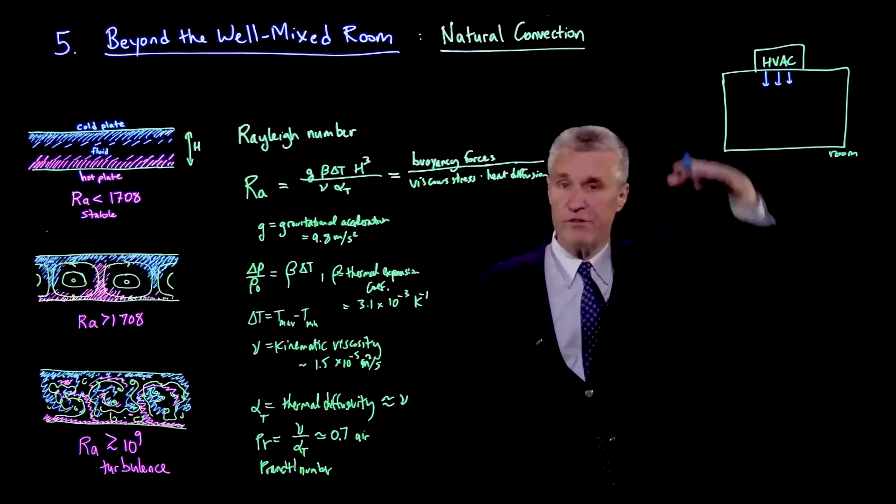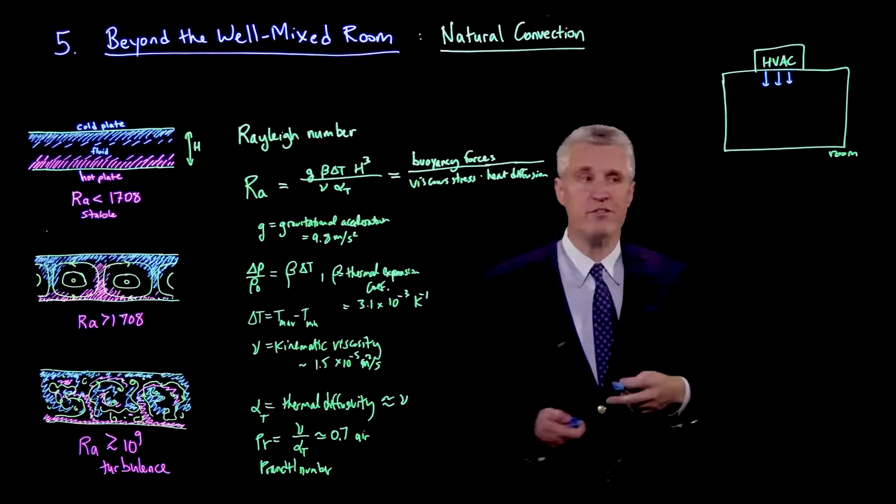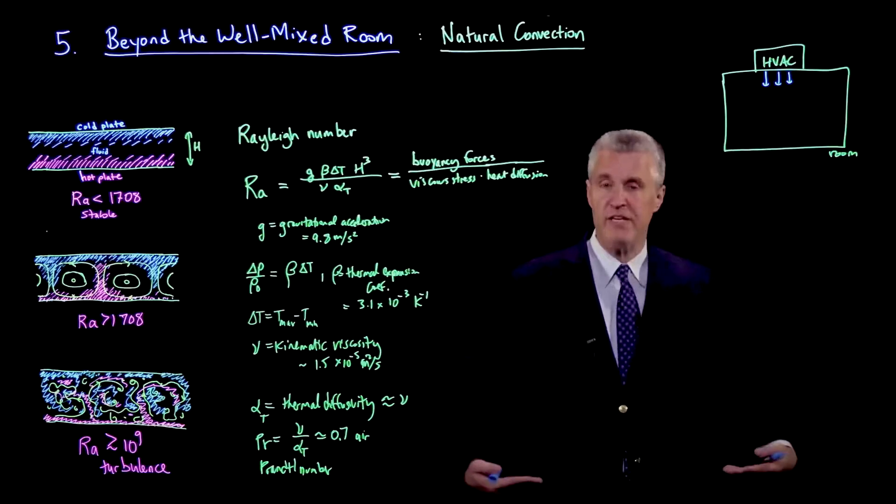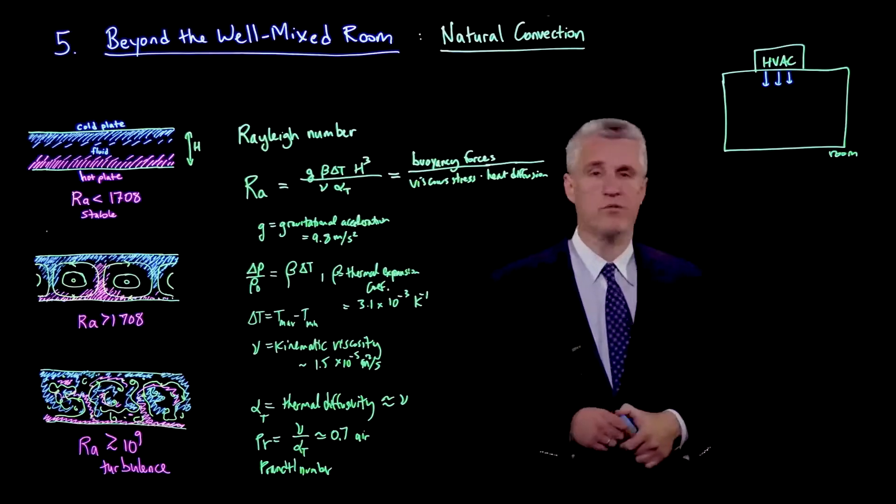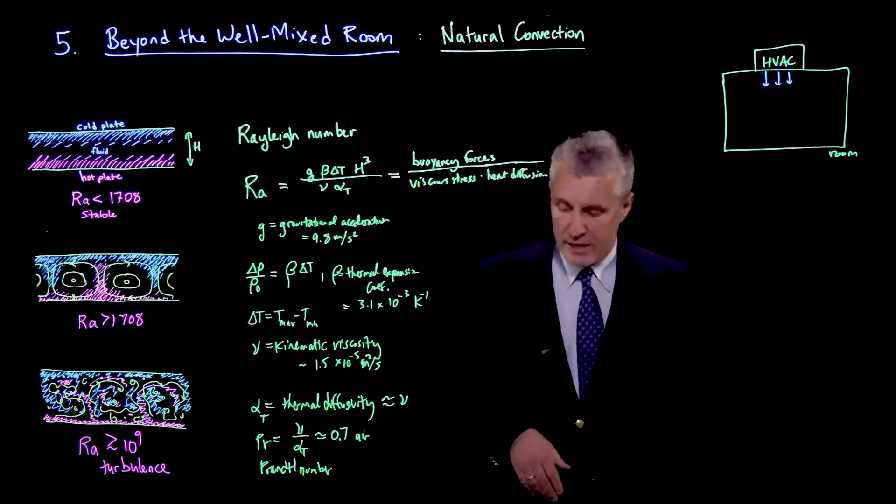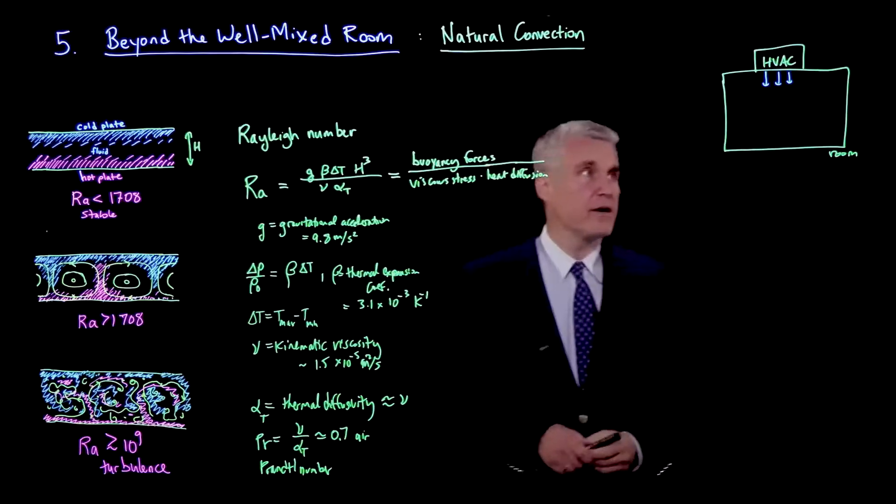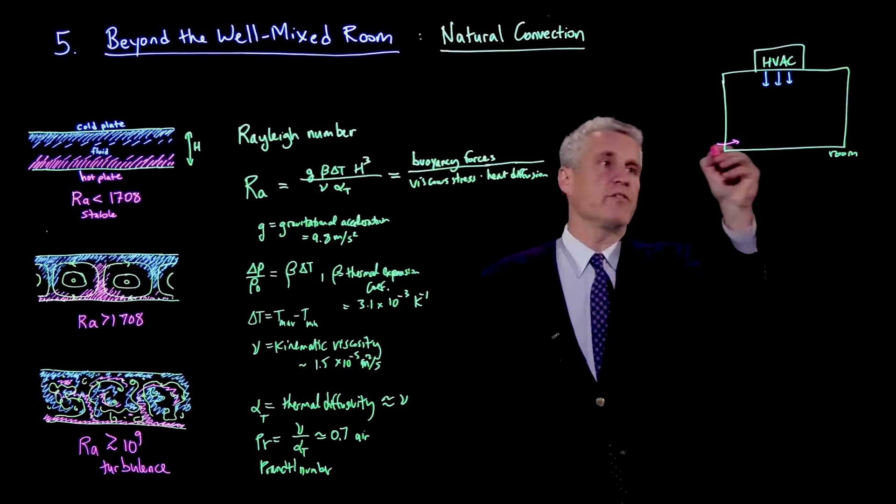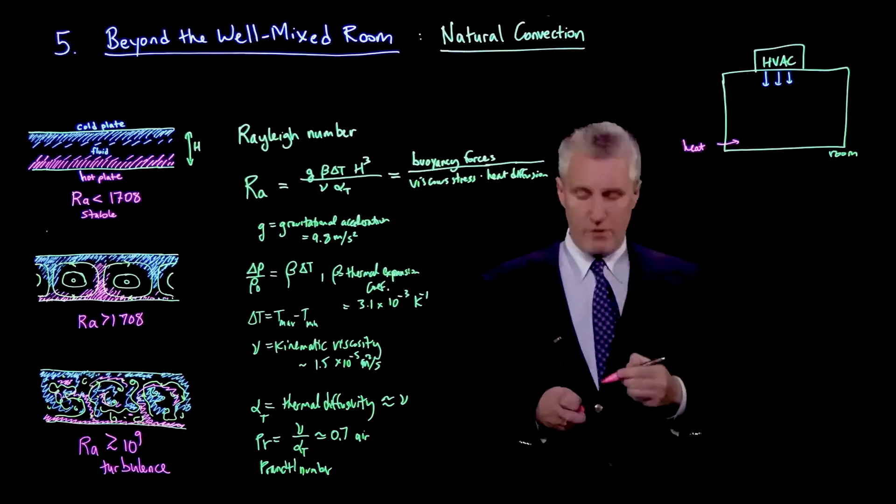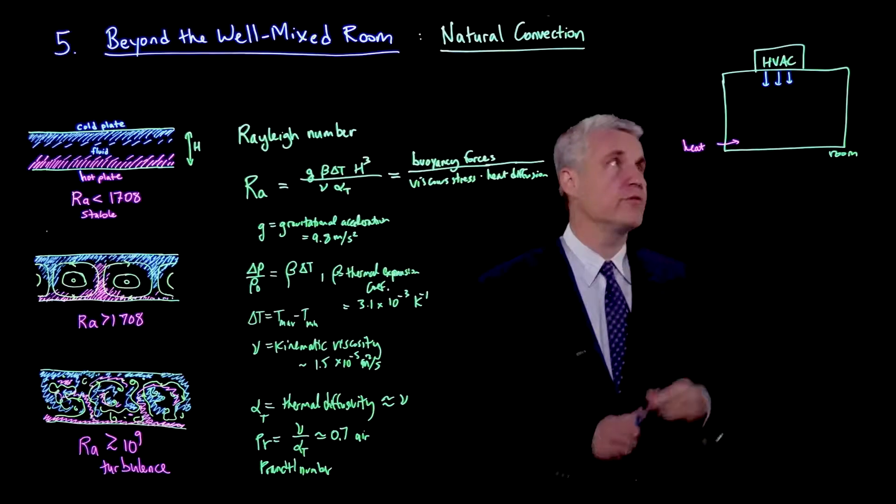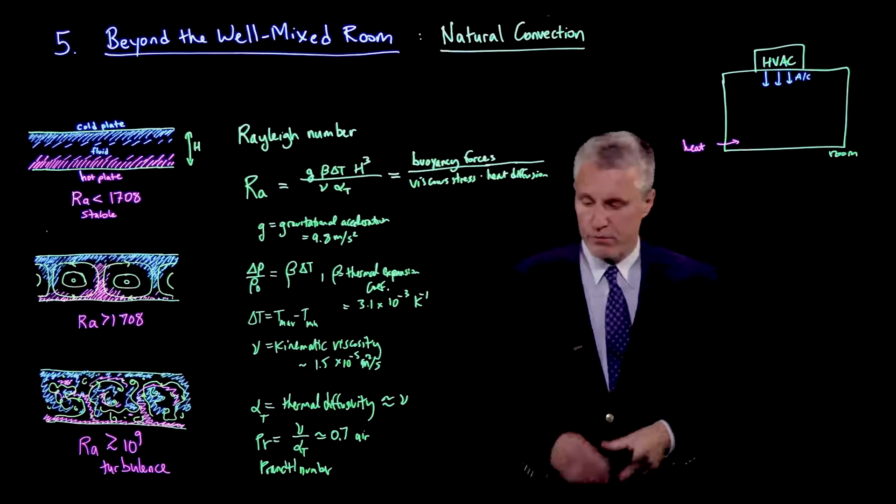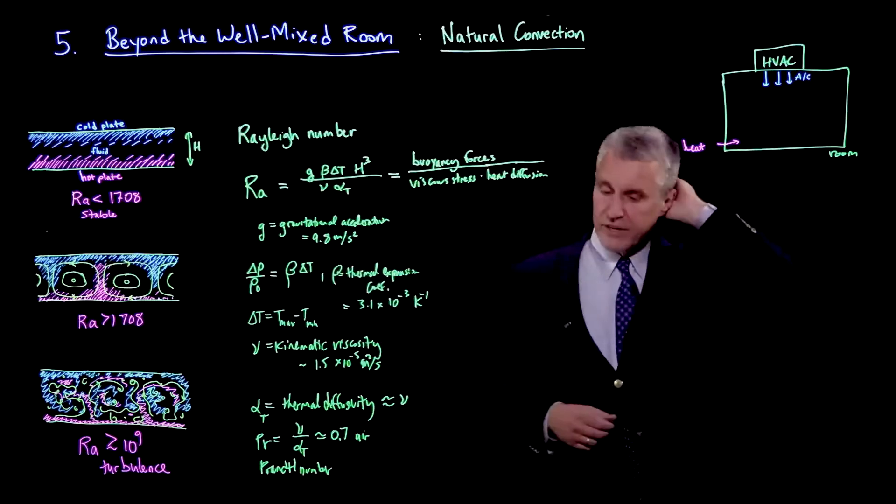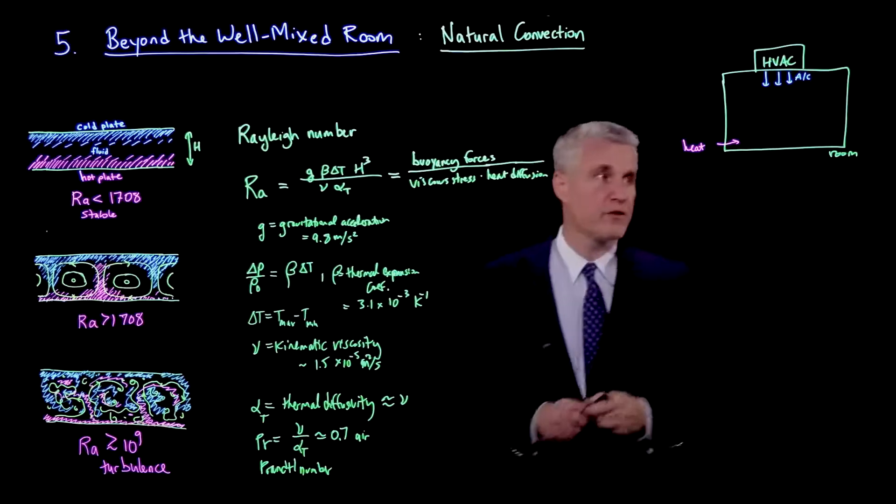We're injecting cold air, and we usually put it on top because we actually want good mixing in the room. That's how these systems are designed. We also inject heat normally from below, for example from the lower sections of the wall or from the floor. If we were to heat, we would do that. And if we're doing air conditioning or cooling, we would do it from above. So basically, there is an unstable gradient like this.